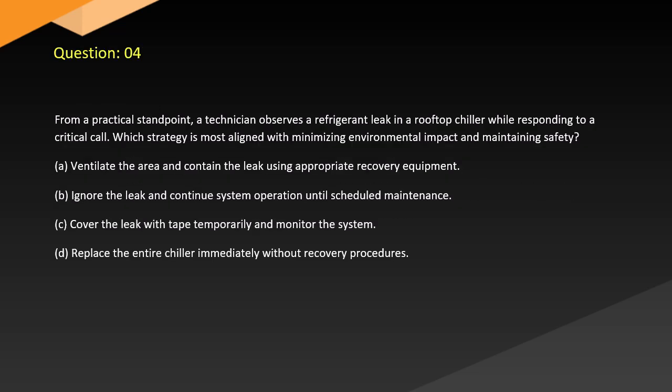Question 4. From a practical standpoint, a technician observes a refrigerant leak in a rooftop chiller while responding to a critical call. Which strategy is most aligned with minimizing environmental impact and maintaining safety? A. Ventilate the area and contain the leak using appropriate recovery equipment. B. Ignore the leak and continue system operation until scheduled maintenance. C. Cover the leak with tape temporarily and monitor the system. D. Replace the entire chiller immediately without recovery procedures.